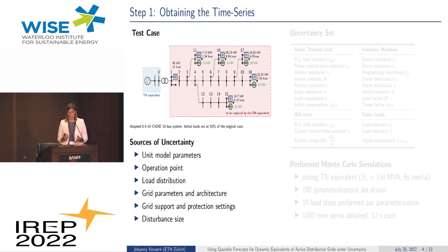The grid that we've been basing this on was a 0.4 kV grid from CIGRE that you can see here on the top left. We have very recent load models and PV models in this, both capable of supporting frequency and voltage. Furthermore, we have modeled all of the standard protection in them. We applied the Australian grid code there because they have one for this very low voltage level, and they also incorporate batteries, which we have then used for load parameterization.